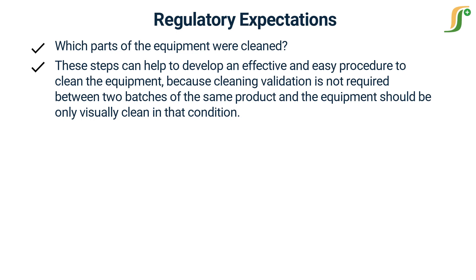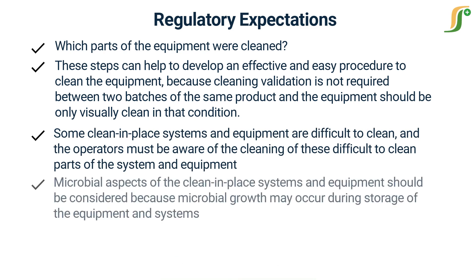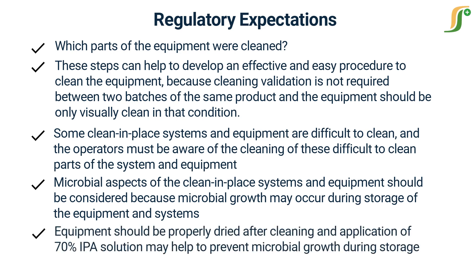Some clean-in-place systems and equipment are difficult to clean, and operators must be aware of the cleaning of these difficult-to-clean parts. Microbial aspects of clean-in-place systems and equipment should be considered, because microbial growth may occur during storage. Equipment should be properly dried after cleaning, and application of a 70% IPA solution may help to prevent microbial growth during storage.